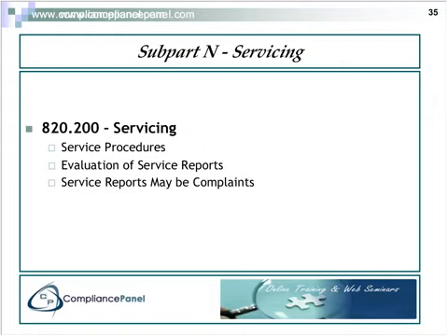And any service reports that you do must contain the name and serial number of the device, the date the service was performed, the name of the person who performed the service, the service performed, and a copy of the test results of the device if applicable.